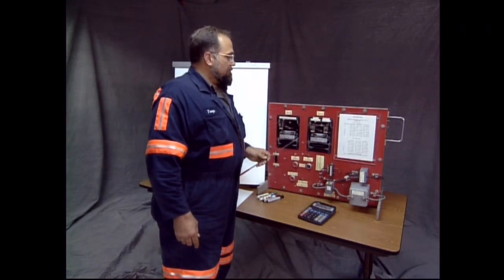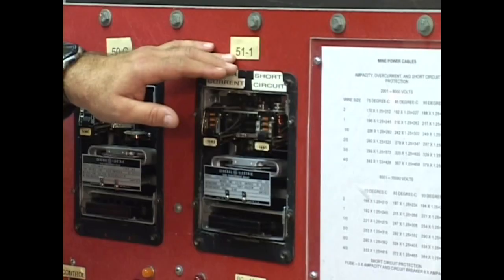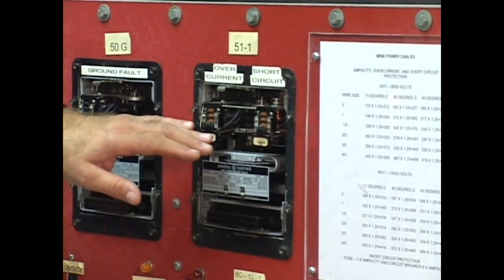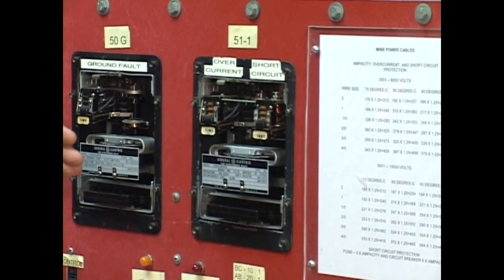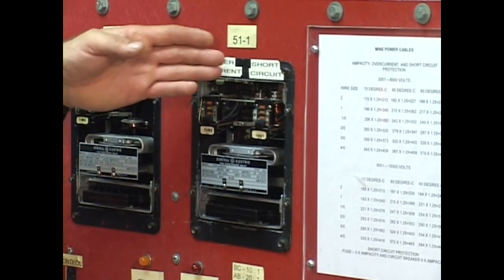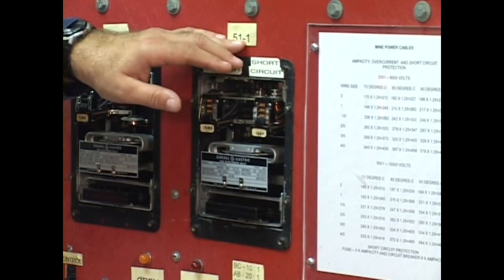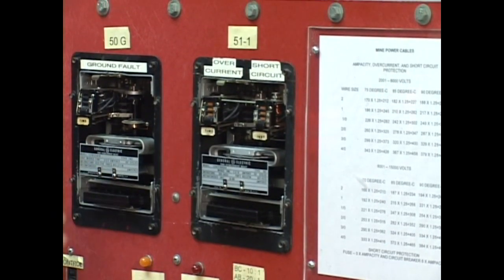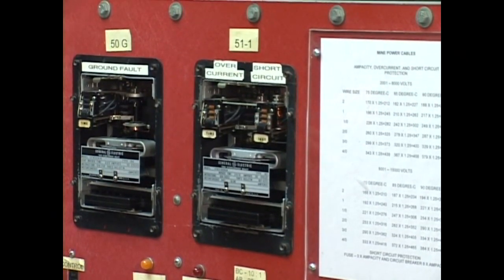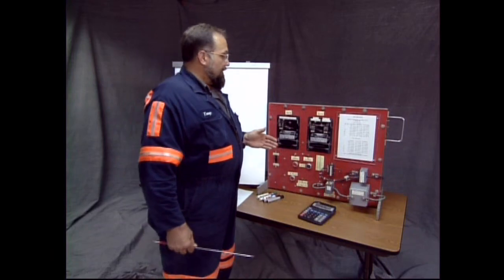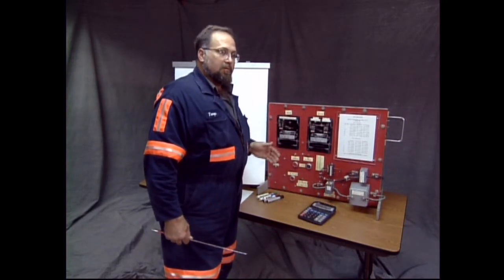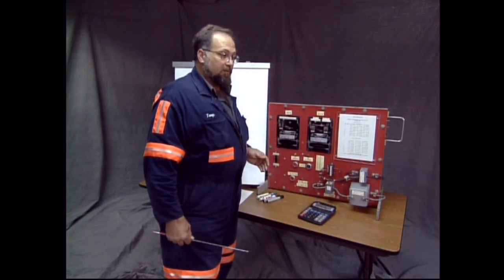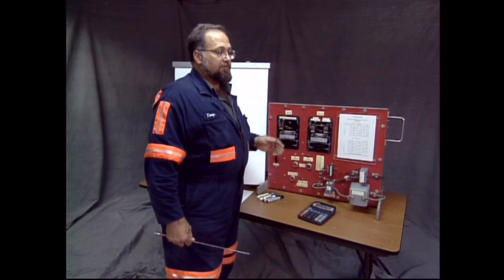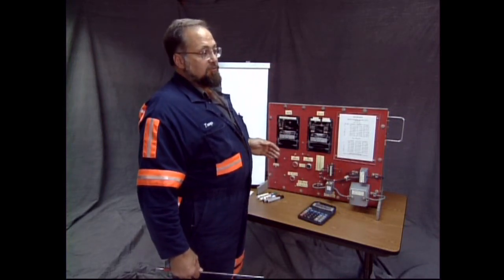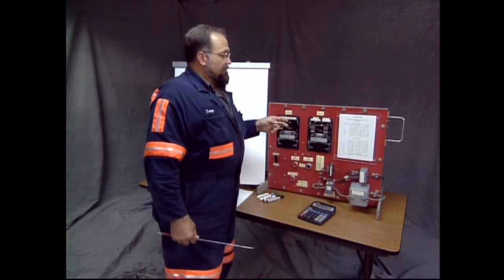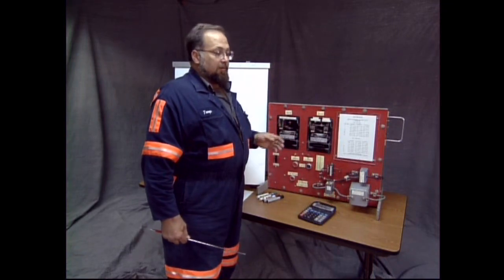Device 51. It has both time and instantaneous. One is for overcurrent, one is for short circuit. The one, it's phase one. On a real substation out in the field, you would have a device 51-1, a device 51-2, and a device 51-3, one for each phase. On an underground station, you would probably only have two, 51-1 and 51-3.